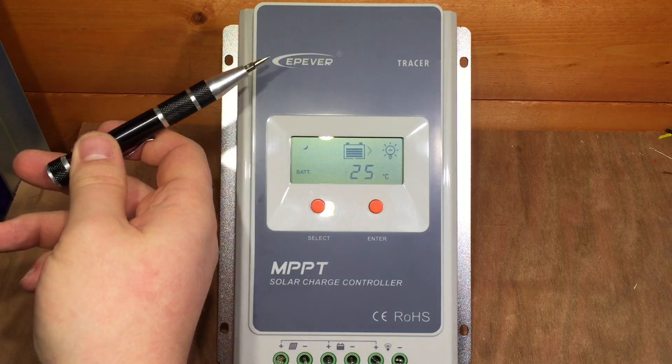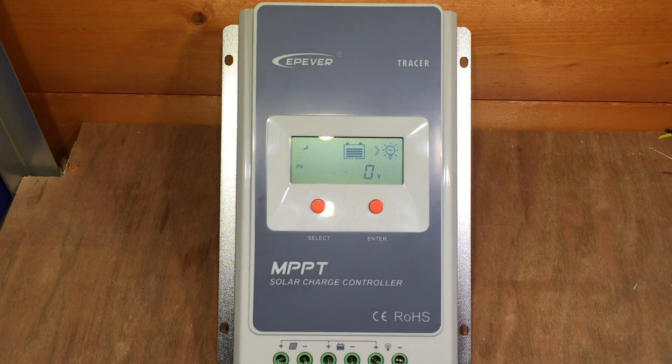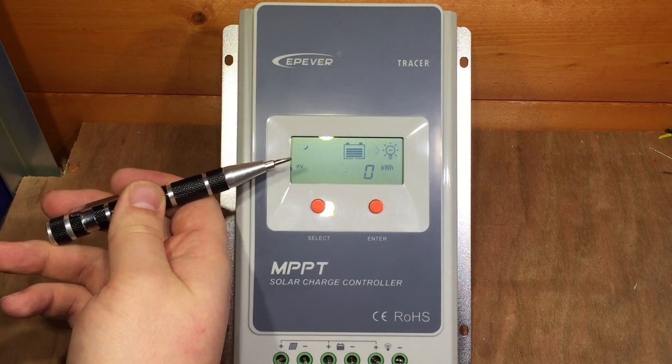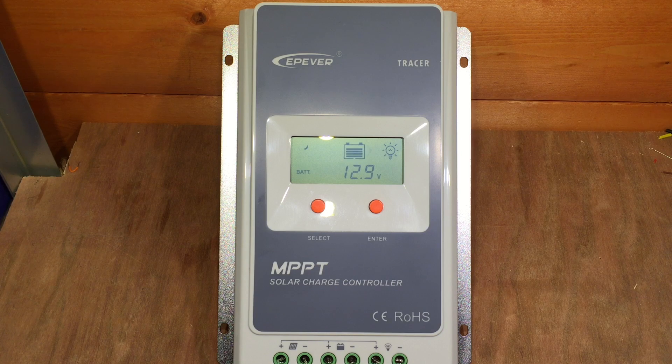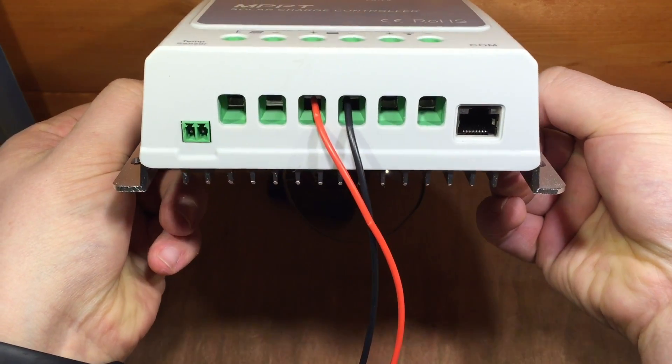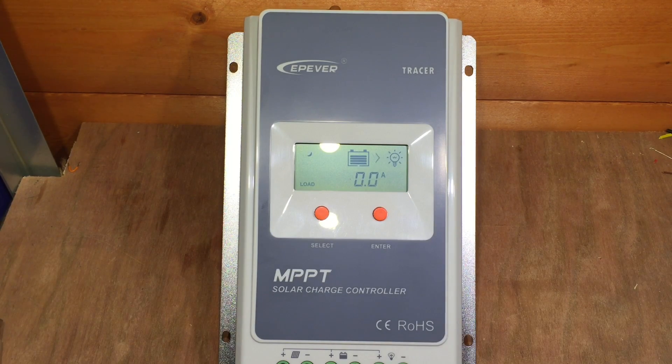The EPEVER Tracer A series seems really good value. It's the only one of the Tracer series where you get a screen and don't need to buy the external screen. There's only a limited amount of things you can adjust with this screen — you do need the MT50 remote meter to change battery voltage and similar settings using the RS-485 port. However, you can also use a USB adapter and a program available from EP-Solar, and in another video I'm going to look at that. Hopefully you've enjoyed this little review — please give me a thumbs up, subscribe, and I'll see you next time. Thanks for watching.